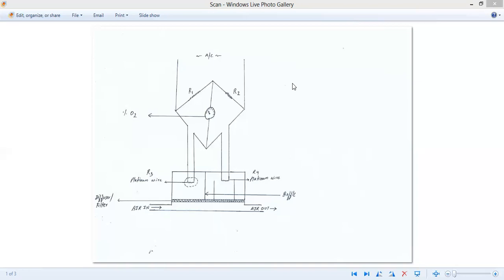Like all gas meters, this oxygen analyzer works on the principle of Wheatstone's bridge. In the Wheatstone bridge, let's go to this diagram. There are four resistances: R1, R2, R3, and R4. If R1 by R2 is equal to R3 by R4, then there won't be any current flowing in the Wheatstone bridge. The bridge is said to be balanced, and inside this galvanometer there will be no movement of the needle. The reading will be zero.